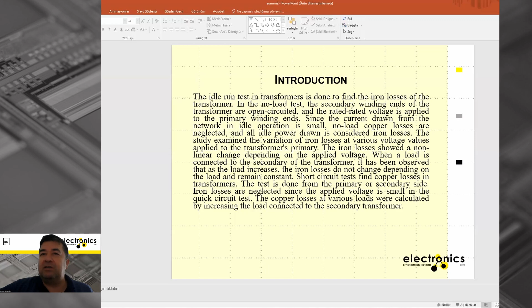The short circuit test finds copper losses in the transformer. The test is done from the primary or secondary side of the transformer. Iron losses are neglected since the applied voltage is small in the short circuit test. The copper losses at various loads were calculated by increasing the load connected to the secondary of the transformer.